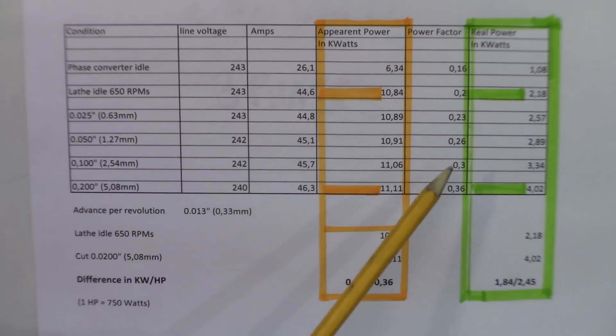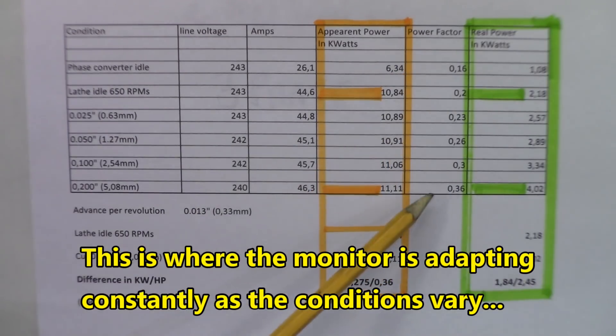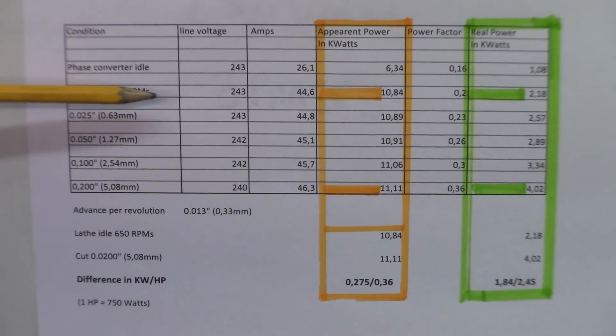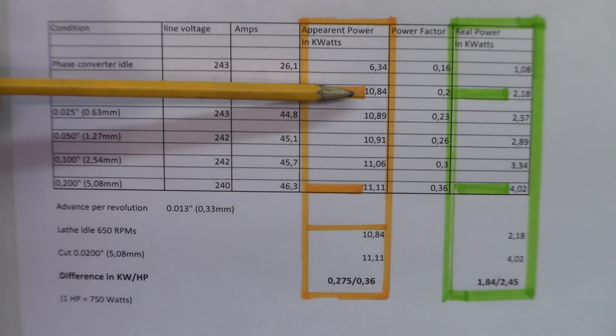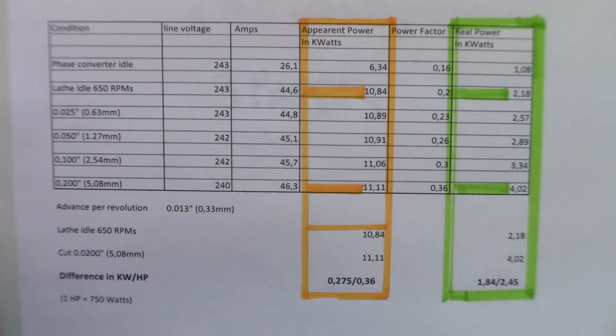This means that if you make the difference, the lathe is idling right there at 10 kilowatts apparent power. And we're taking a 200 thousandths cut, which is a 5 millimeter cut, and the figures will be like 11.1 kilowatt. So if you make the difference between those two figures here, I even gave you a HP figure too, but the first number, difference in kilowatts and HP, the first one here is the number of kilowatts difference between the situation where the lathe is idling and the lathe is taking a 200 thousandths cut or 5 millimeter cut.